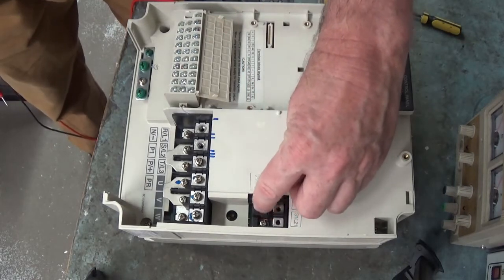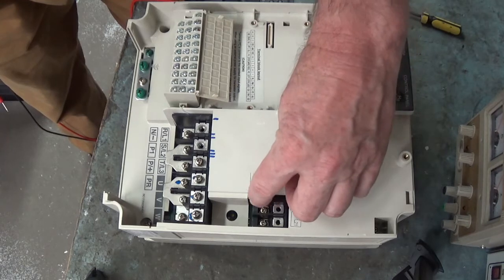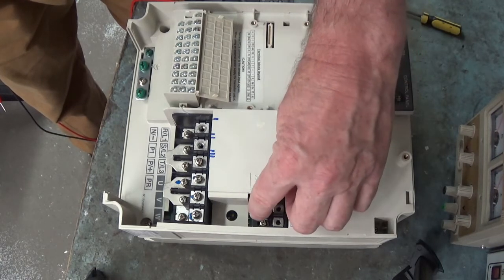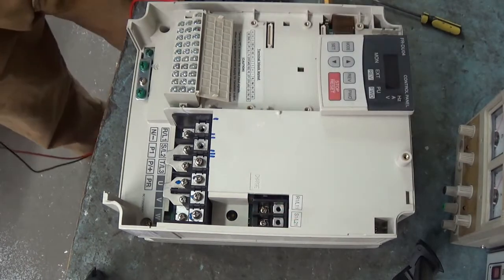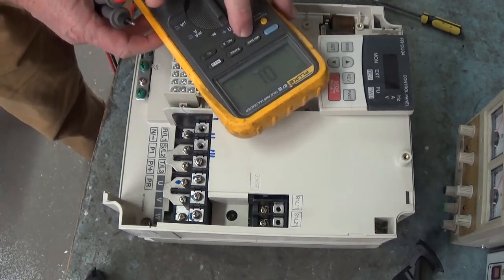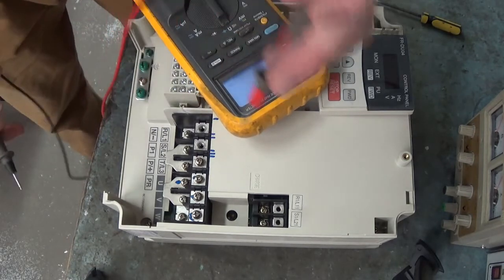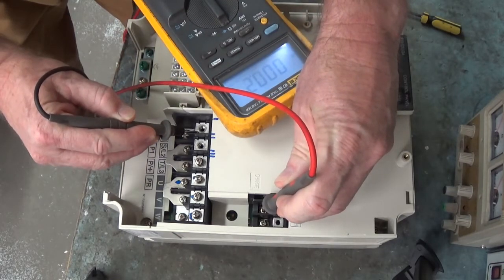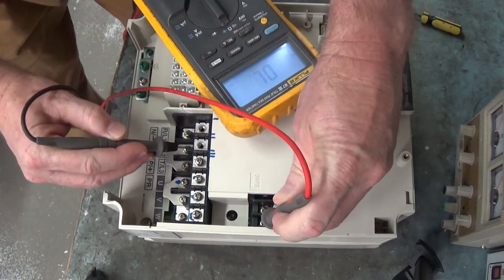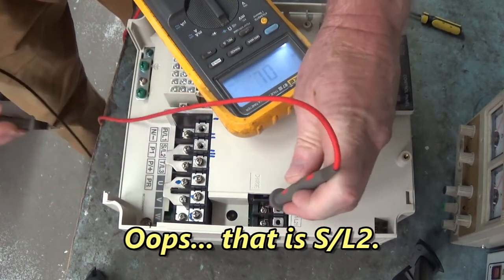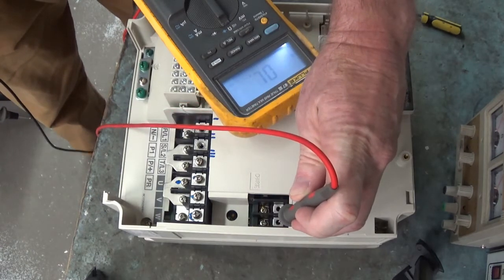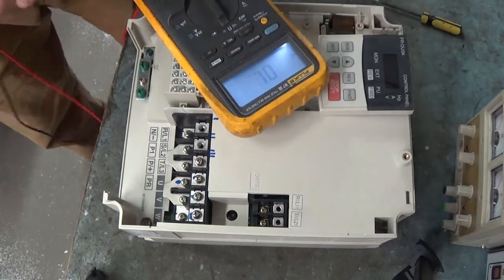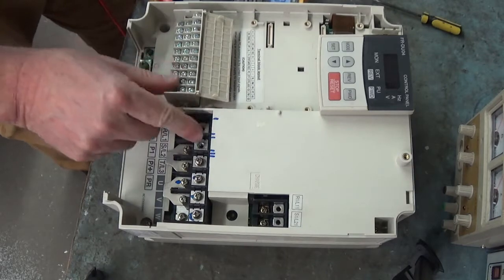Well, do you see those two terminals down there in the bottom? They'll be jumped. This one here will be jumped to the top one, and this one over here will be jumped to that top one. These two terminals down here on the bottom, I'll put my meter in beep mode and I'll show you where they go. These two bottom terminals go right there to R slash L1, and the next one goes to S slash L2. So if you jump this one to that one and jump this one to that one, you're connecting the control switch mode power supply to the line voltage.